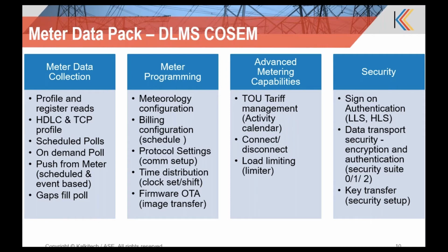And last but not least, for meter programming, we have support for firmware update over the air. For the meter firmware, we use the image transfer IC available in the standard. Using the DLMS standard and the image transfer IC, the firmware of the meter can be transferred from the headend to multiple meters in a single shot.